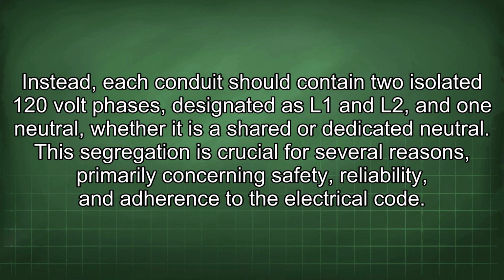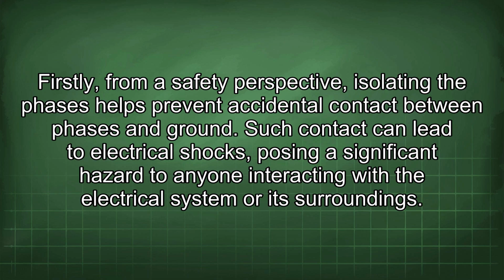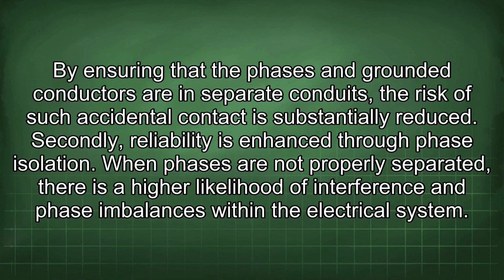Instead, each conduit should contain two isolated 120 volt phases, designated as L1 and L2, and one neutral, whether it is a shared or dedicated neutral. This segregation is crucial for several reasons, primarily concerning safety, reliability, and adherence to the electrical code. Firstly, from a safety perspective, isolating the phases helps prevent accidental contact between phases and ground. Such contact can lead to electrical shocks, posing a significant hazard to anyone interacting with the electrical system or its surroundings. By ensuring that the phases and grounded conductors are in separate conduits, the risk of such accidental contact is substantially reduced.